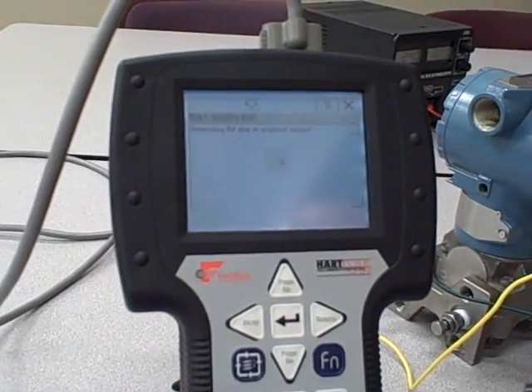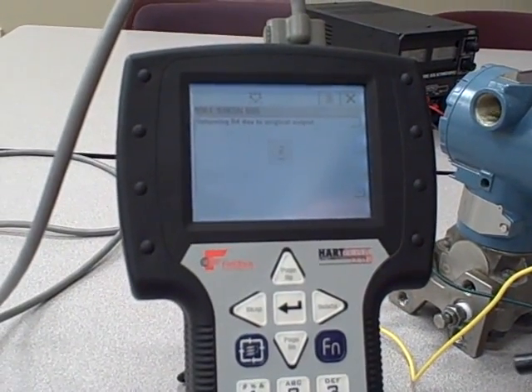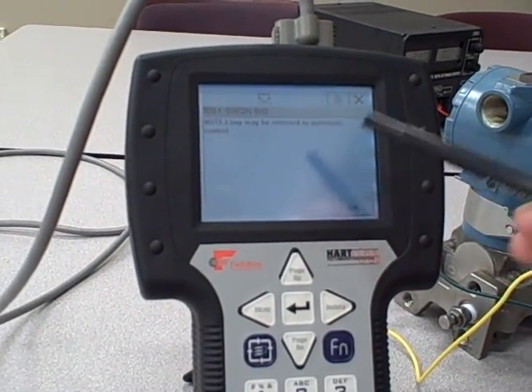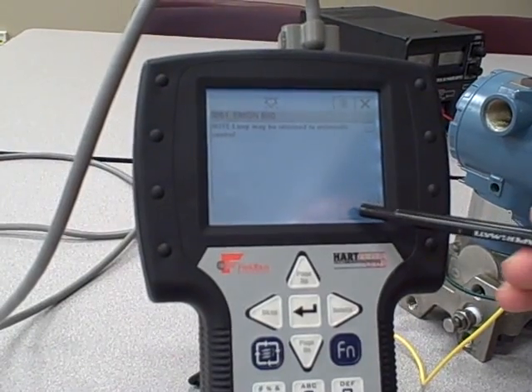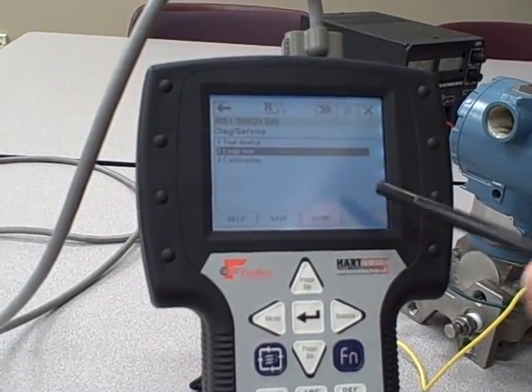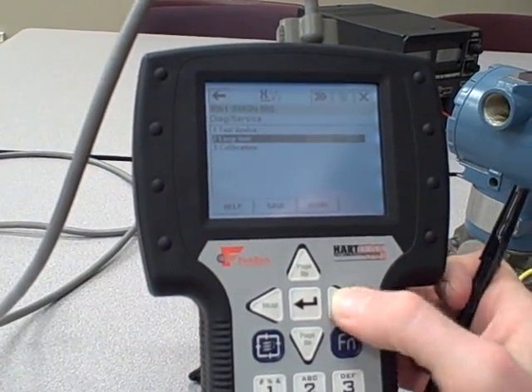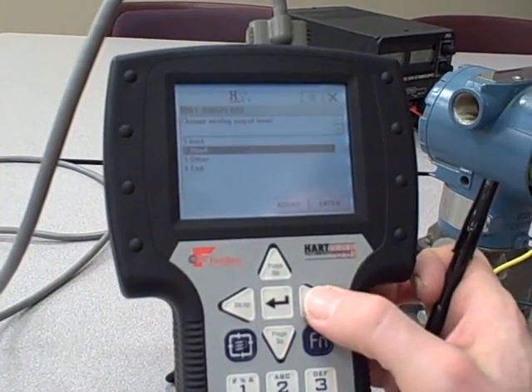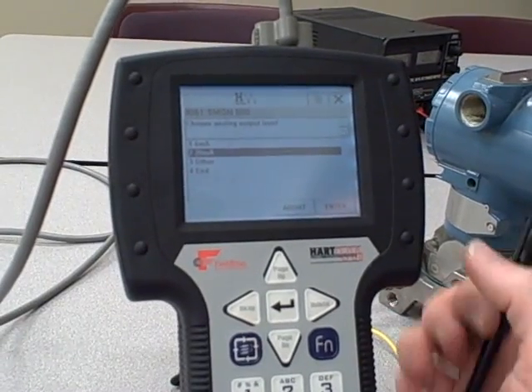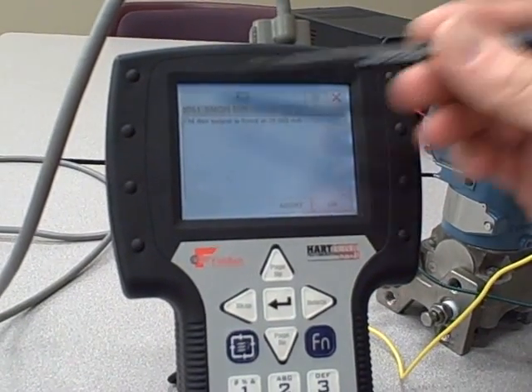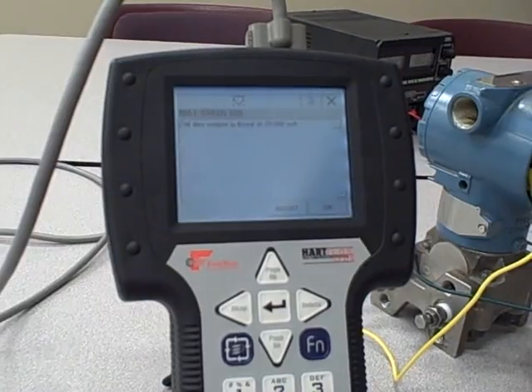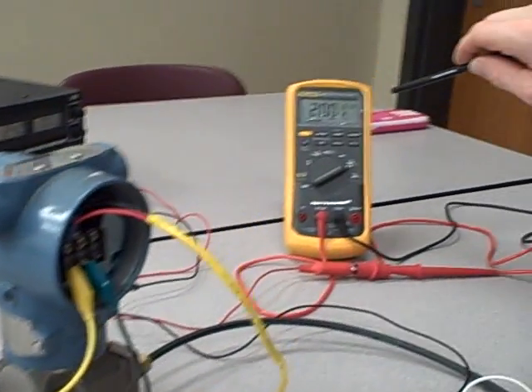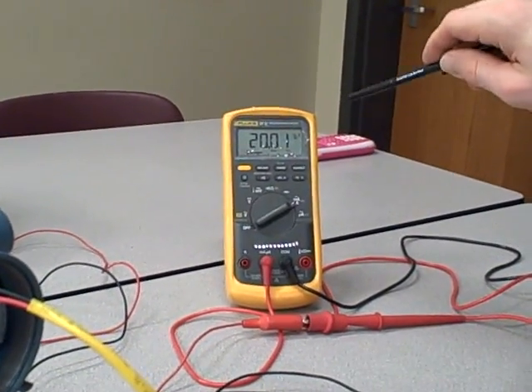Going back here, I can abort that test. It gives me another warning - loop may be returned to automatic control. I can go back into loop test and tell it to go to 20 milliamps. It says here, field device output is fixed at 20 milliamps. And there we go, 20 milliamps indicated on our Fluke meter.